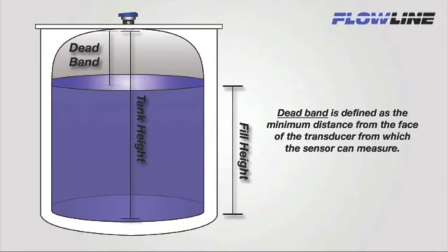Deadband is defined as the minimum distance from the face of the transducer from which the sensor can measure. Liquid level should never be allowed to rise into the sensor's deadband. To eliminate conflicts, the deadband is automatically subtracted from the fill height. For example, if the sensor range is 295 inches with an 8-inch deadband, the maximum fill height would be 287 inches. We get 287 inches by subtracting the 8-inch deadband from our total sensor range of 295 inches.